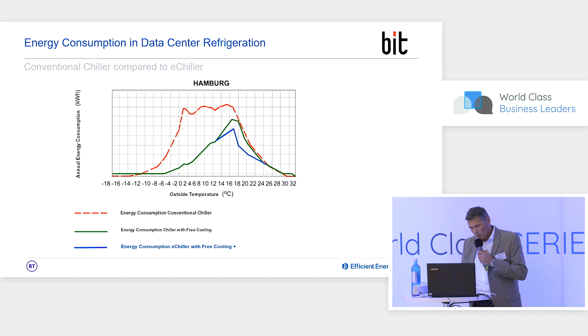Especially if you're doing that with special kinds of chillers, for example the e-chiller from Efficient Energy. You get an extended version of free cooling, that's the blue line, because you don't have to switch or decide whether you're using free cooling or not. With these chillers, you can pre-cool the water using the rest of the usable outdoor temperature energy, and then additionally cool it by the compressor.